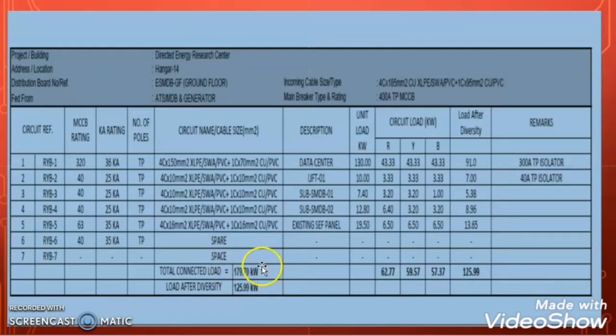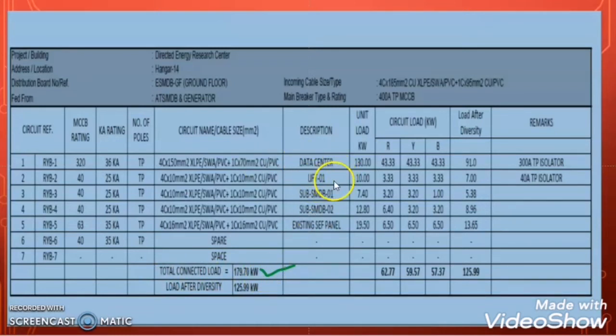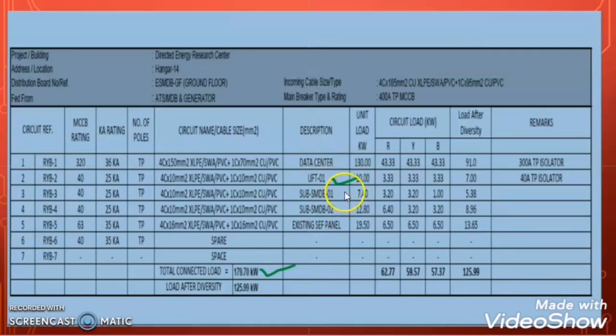But if we size the DG set based on the total connected load of 179.7 kW, our DG set will be oversized. This is because all loads will not be operational at the same time — for example, the lift will be at rest unless someone is using it, and the smoke extract fan will only operate during a fire or a test that produces smoke. So the total connected load is 179 kW, but the actual running load at any given time is less.